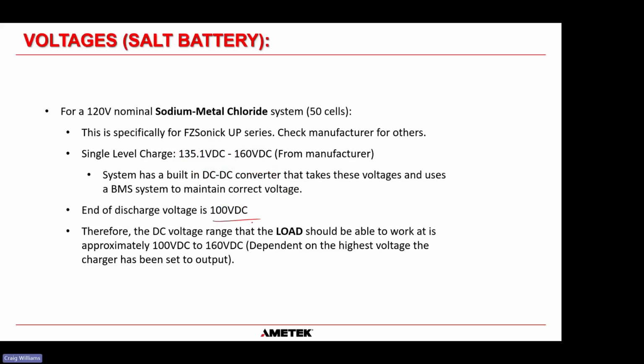The end of discharge voltage is 100 volts. So therefore, your load should be able to work anywhere between 100 volts DC. I've said here to 160 volts because the manufacturer says you can go up to that. But if you set your charger voltage to never go above 140 volts, then you can say it's going to be 100 volts to 140 volts, very similar to a lead acid battery.